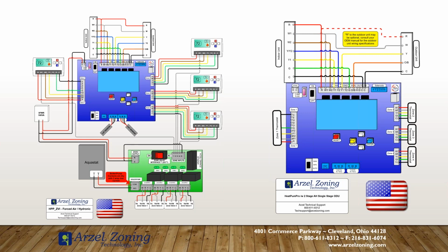The Heat Pump Pro does not have that feature. Every thermostat is master. However, if you need to test the system, maybe you're doing your startup testing, you don't want your customer to be able to turn off a thermostat and screw up your testing numbers. You want everything to stay open.